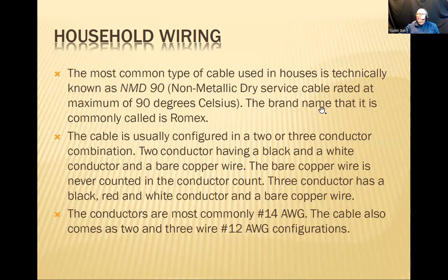Excuse me, the brand name that is commonly called Romex, which I just explained. The cable is usually configured in a 2 or 3 conductor combination, the conductors being a black and a white conductor and the bare copper wire. The bare copper wire is never counted in the conductor count, which I explained probably extensively in the last few minutes. Three conductor has 3 conductors. So let's say whatever three conductor has a black, red, and white conductor and a bare copper wire. So it has 4 conductors really, but we're just counting the current carrying conductors.